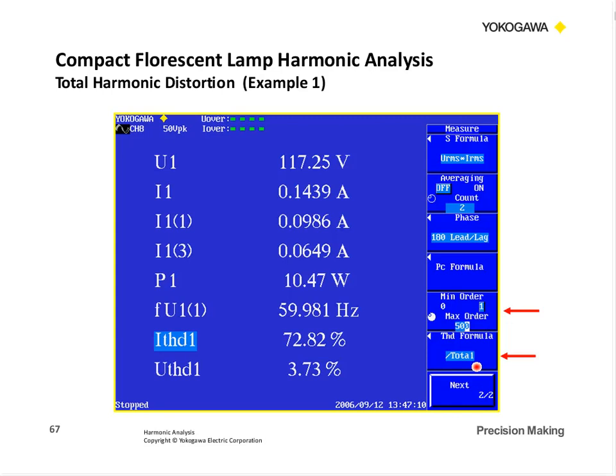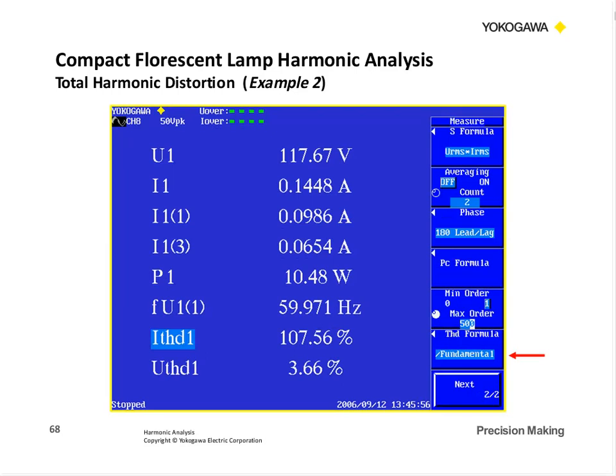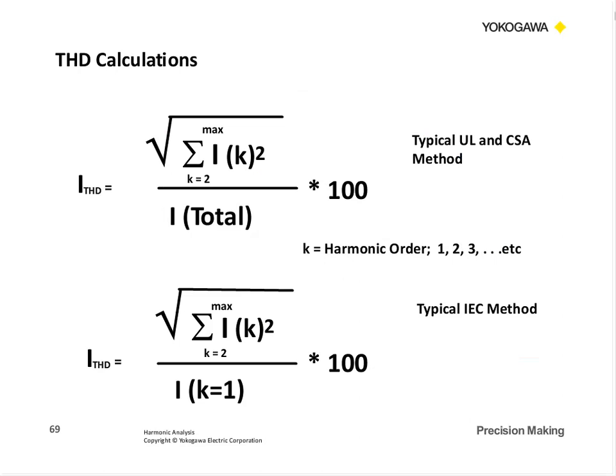Two ways of doing it: divide by the total, or divide by the fundamental. And in these two examples, we have both calculation methods available to you. Typically our UL and CSA method like to divide by the total RMS value. The IEC method defines it as dividing by the fundamental. So we give you both methods.